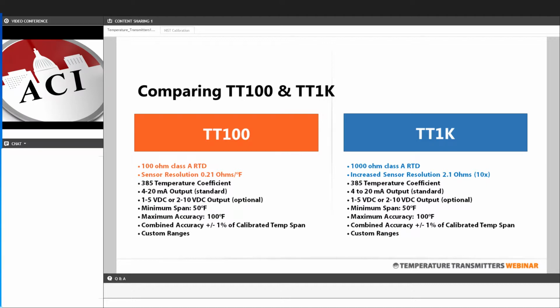The combined accuracy between the sensor and transmitter, so the total accuracy of these devices, is going to be 1% or better. And like I mentioned a second ago, all of these are calibrated per order to the specific temperature span that you require for your application.